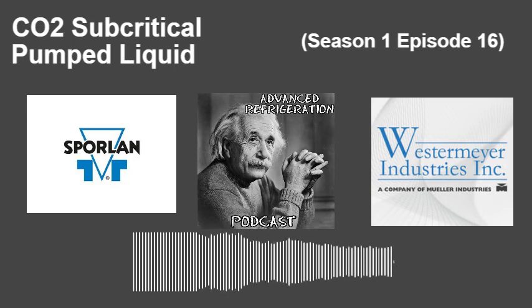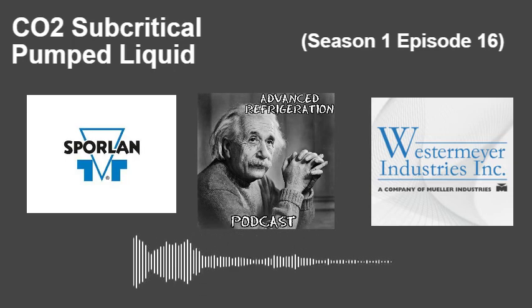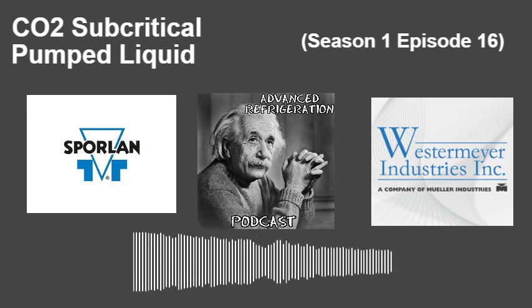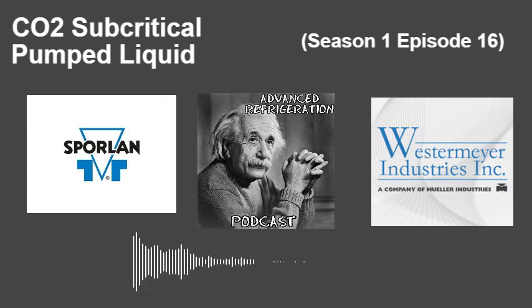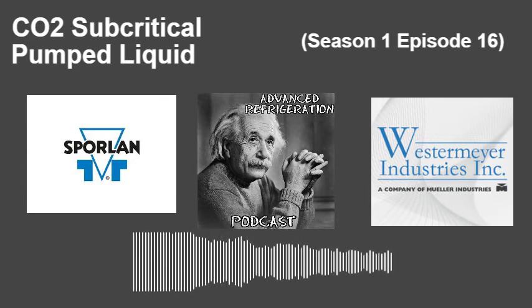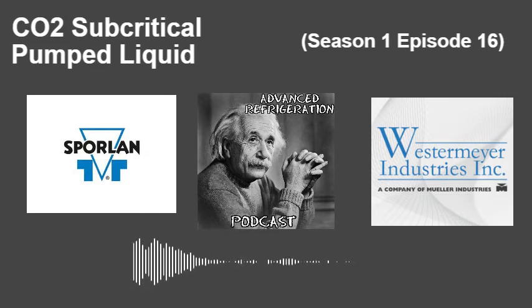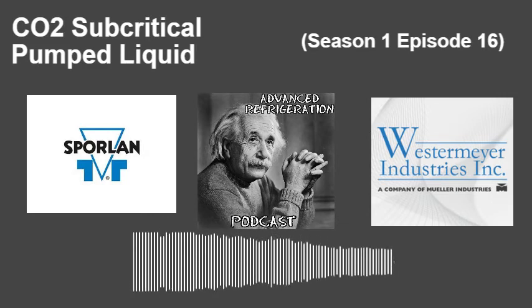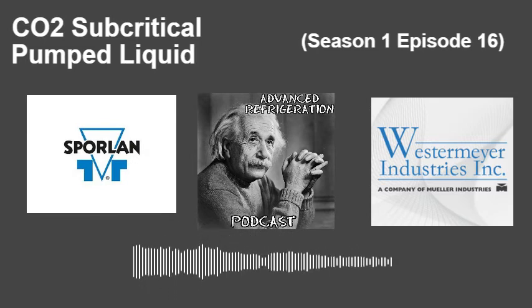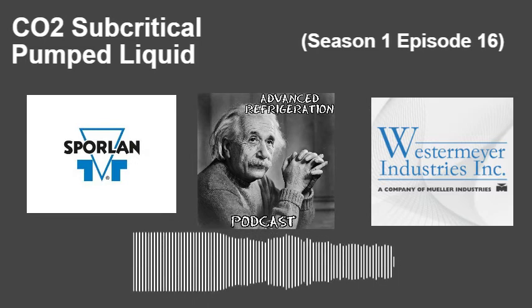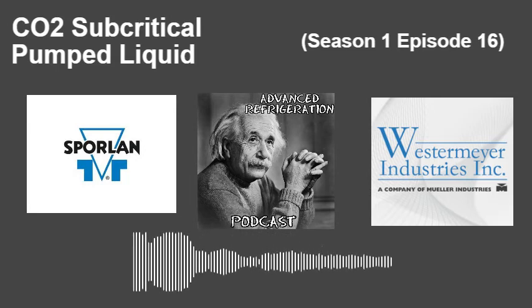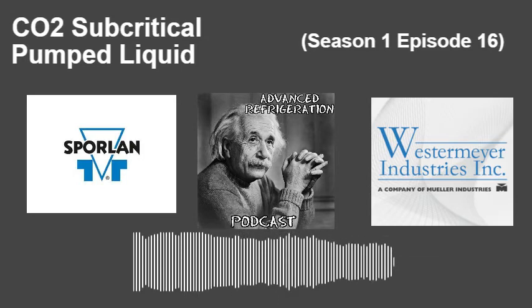If you're really desperate, you're going to have to heat up the tanks with a torch a little bit. The supplier is not going to like that. But if you need to get every bit out of there, you need to get every bit out of there. So you want to get that vessel as low as you can while you're charging, so you get more CO2 out of those tanks. Those tanks are very heavy, so be very careful. They're like twice as heavy, because of the pressure.